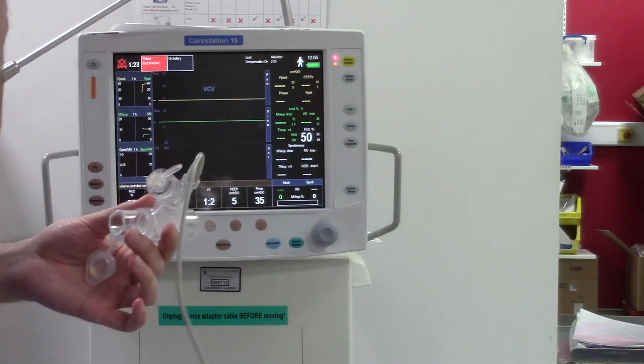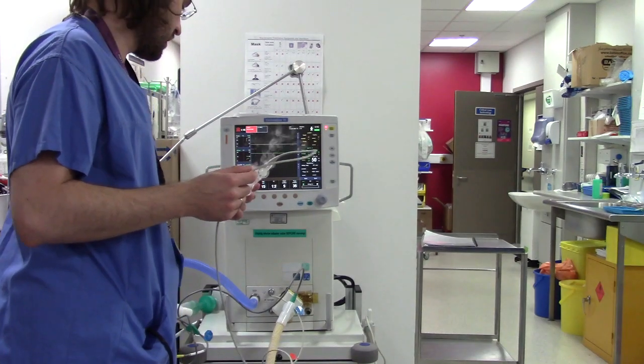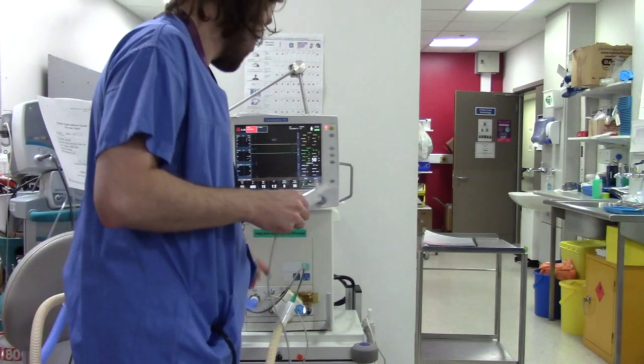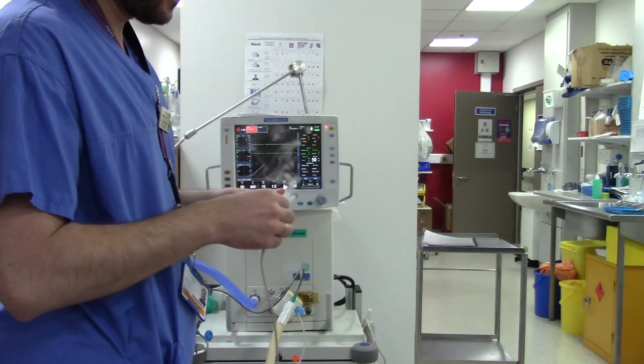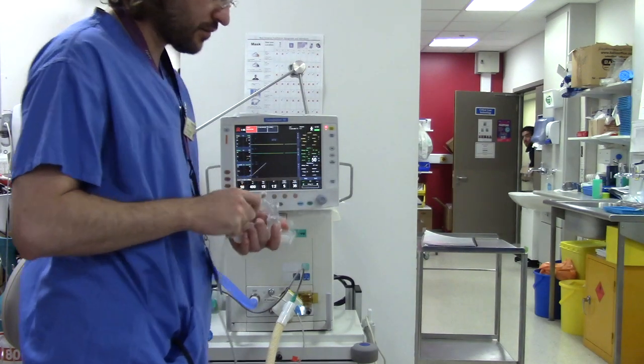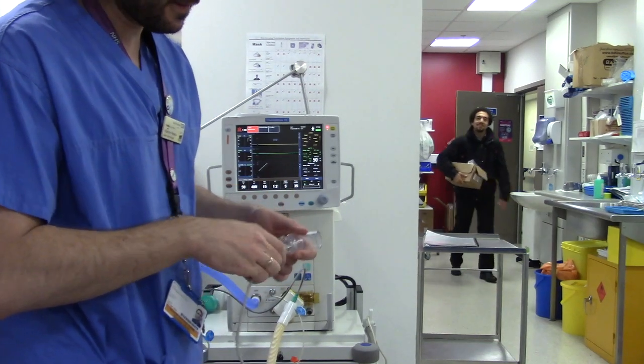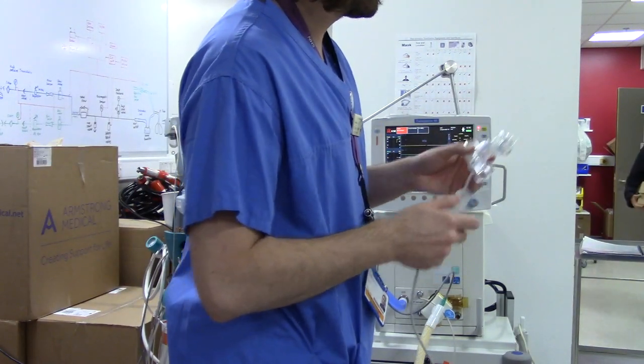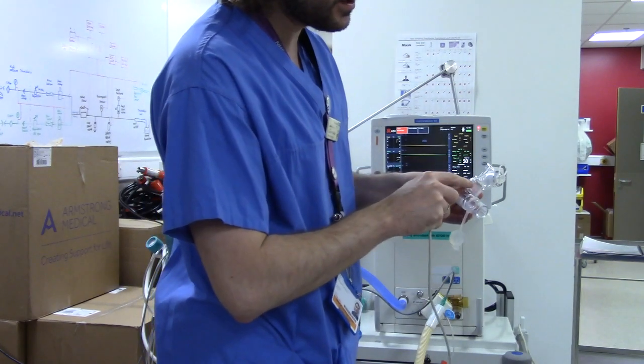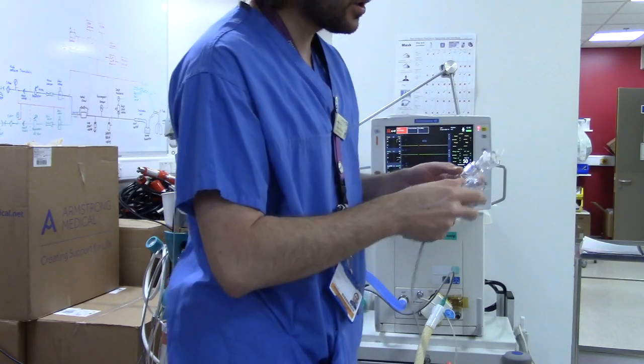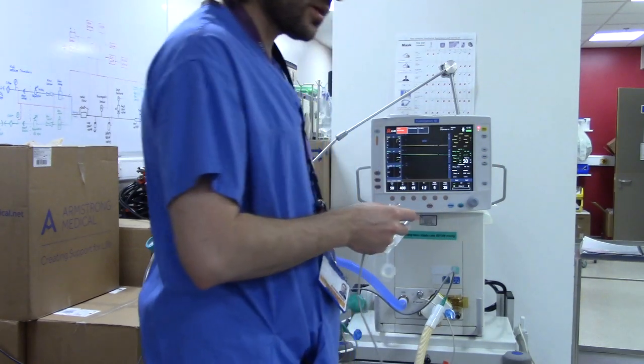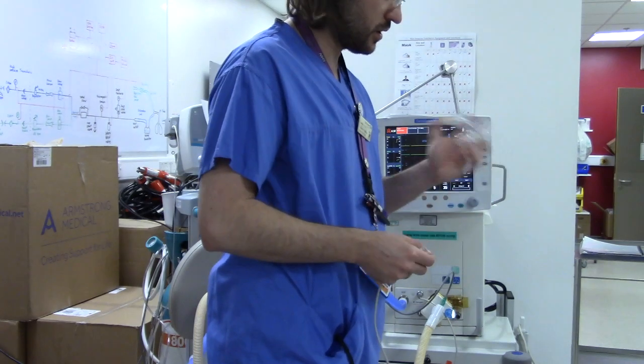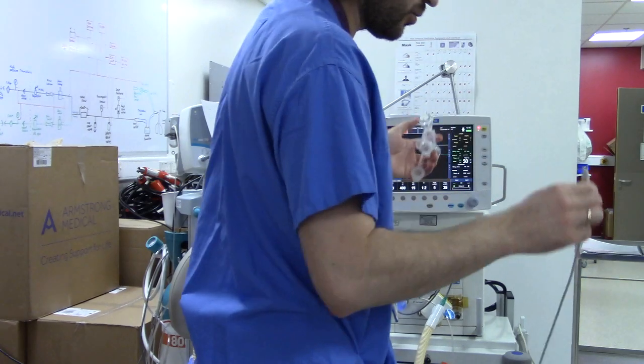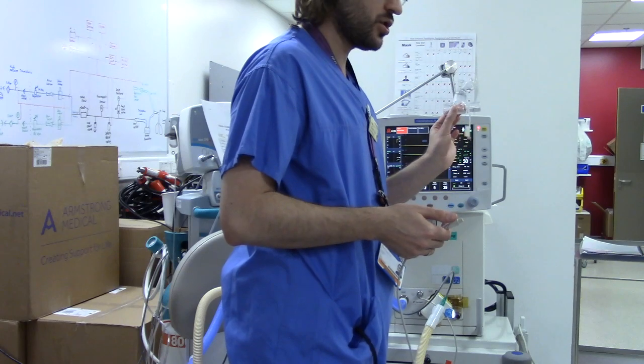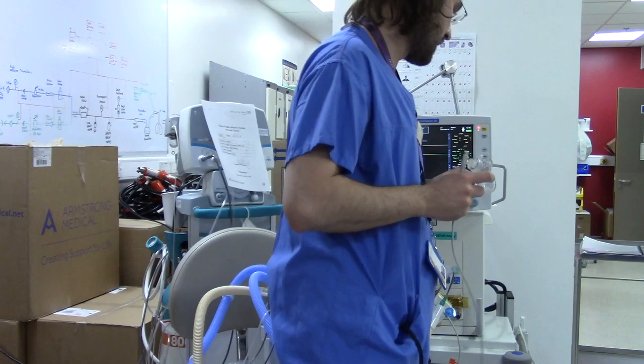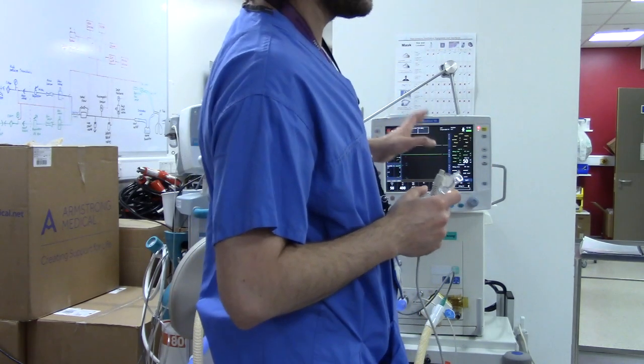What issues you can get with this is mainly that the cables will not be working. They usually fail at this part or this part. If it's not working, you can try fiddling with it to see if it will work. Or you may get some fluid in there, and when you connect it, you don't make a good contact. Or you have an air bubble between the pump and the actual fluid sometimes. What you do is remove it from the circuit, make sure this is closed, and just give it a shake. If that's not working, and it's not working with the new cable, that definitely means you need to change this. It's very, very rare that the actual ventilator has a fault which will not trigger the nebulization. Alright?